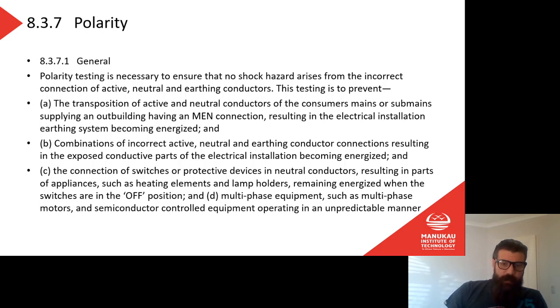What else? Combinations of incorrect active, neutral and earthing conductor connections resulting in the exposed conductive parts of the electrical installation becoming energized. So this is the same thing: if we accidentally connect the phase and the neutral around the wrong way, somewhere other than the switchboard or the mains coming in, so somewhere in the installation, we could accidentally connect live power to metal parts in the installation. Again, let's use that kitchen bench as an example. If I accidentally connected something in my house the wrong way around, I could potentially put live voltage on that kitchen sink.